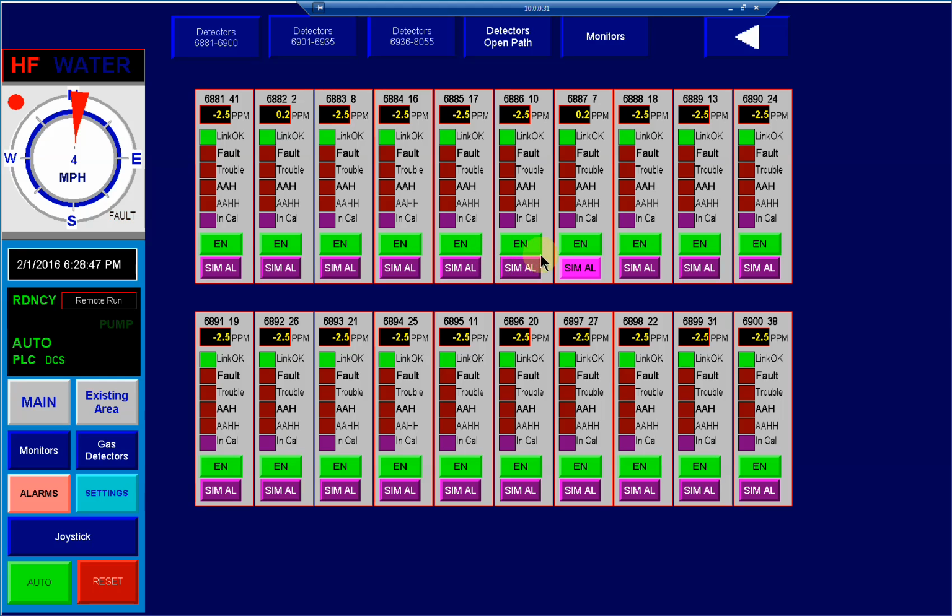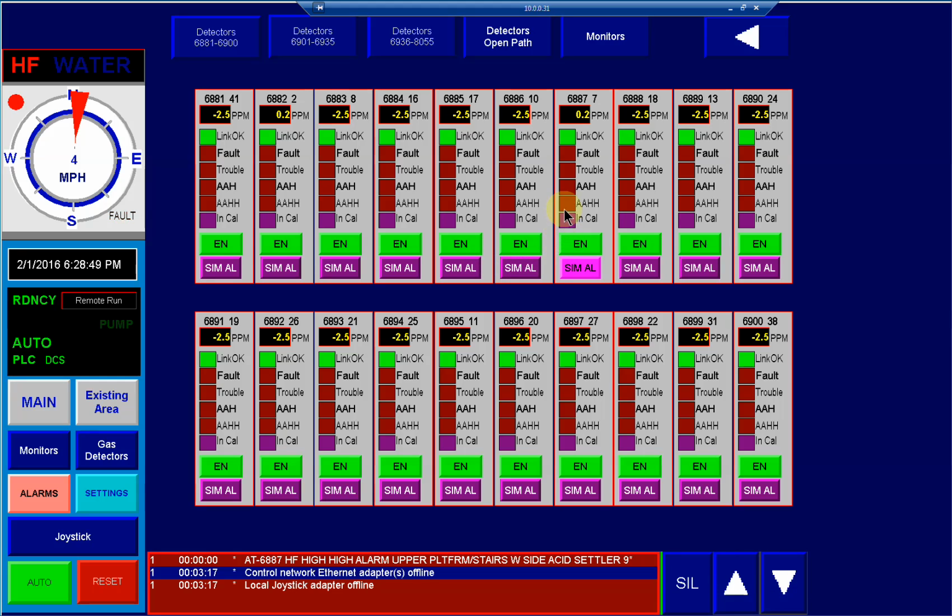We see the high alarm indication, red LED blinking. We also see the alarm detail, with timestamp and exact location. Then the hydrogen fluoride gas leak indicator also blinking red. No water yet. We need another point gas detector to trigger a mitigation event.